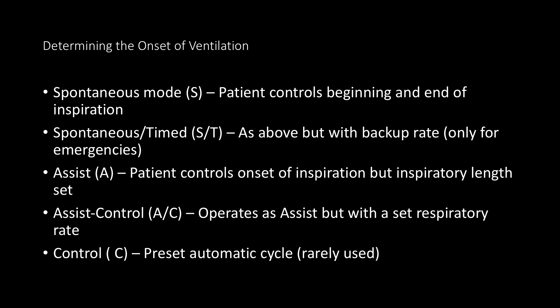Looking at the different ways of determining the onset of ventilation, there are a number of modes available. A spontaneous mode, abbreviated S: the patient controls the beginning and end of inspiration. The spontaneous timed mode, ST, is probably the most commonly used mode on the Philips Respironics device — this is as above but with a backup rate that only kicks in in emergencies, essentially when the patient becomes apneic. The assist mode, A: the patient controls the onset of inspiration, but the inspiratory length is set. Assist control mode, AC: operates as the assist mode but with a set respiratory rate. The control mode, C: a preset automatic cycle, which is rarely used.